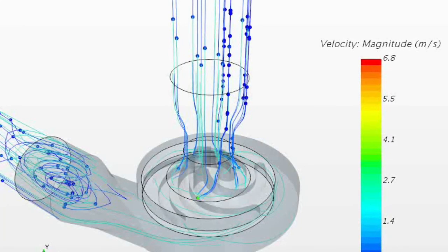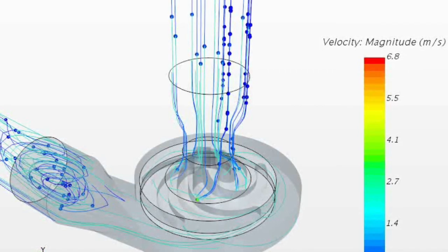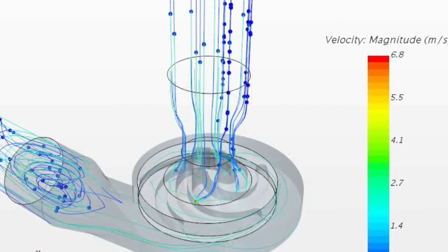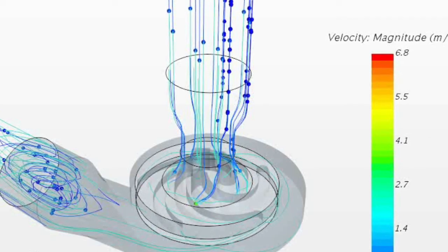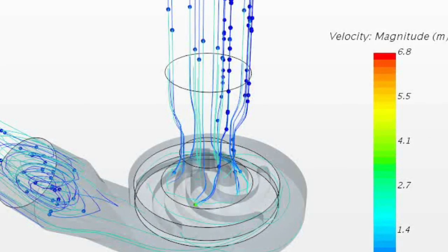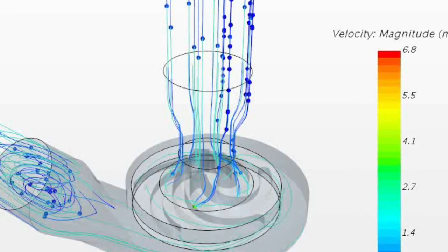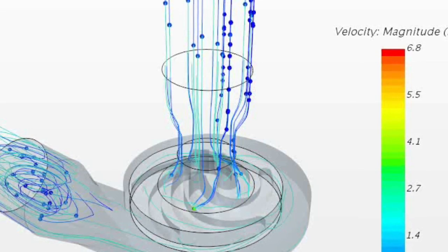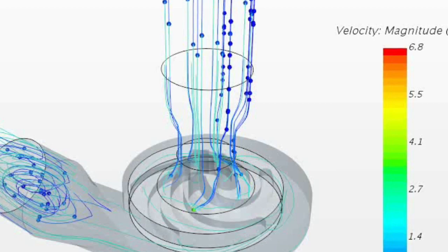As for the simulation in CFD, the results show that with a higher viscosity, a lower total head value was obtained and a bigger power was obtained as well. It was also proven that when the density increases with a constant viscosity, all values for the pump increase too. In contrast, both methods are useful for analyzing the pump's performance, but the CFD simulation includes more fluids with coherent results than the algorithm. This can be due to the fact that the algorithm calculation is designed for water, so when a fluid has a similar value of density and viscosity to the water, the results are more accurate.